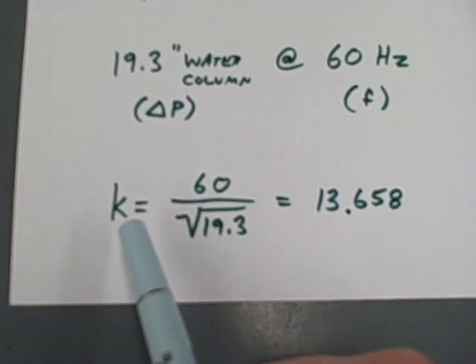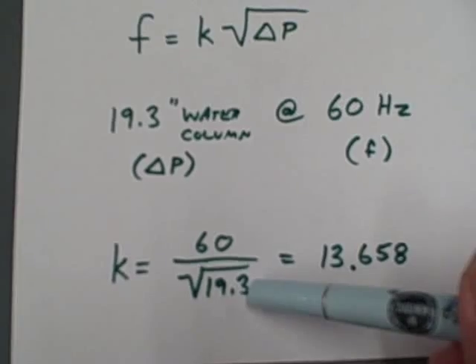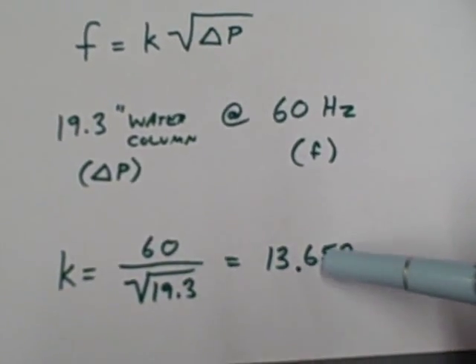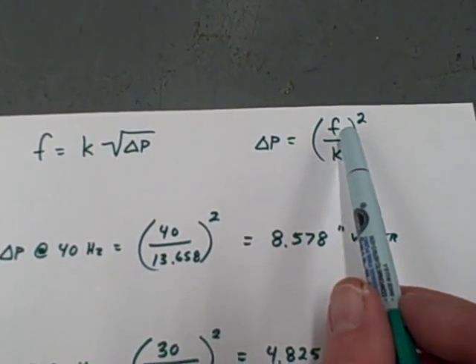Now taking these figures, I calculated a value for k, a constant proportionality, given the frequency and the differential pressure measured earlier. This constant, we can now plug into the equation and solve for the amount of differential pressure given any number of different frequencies.